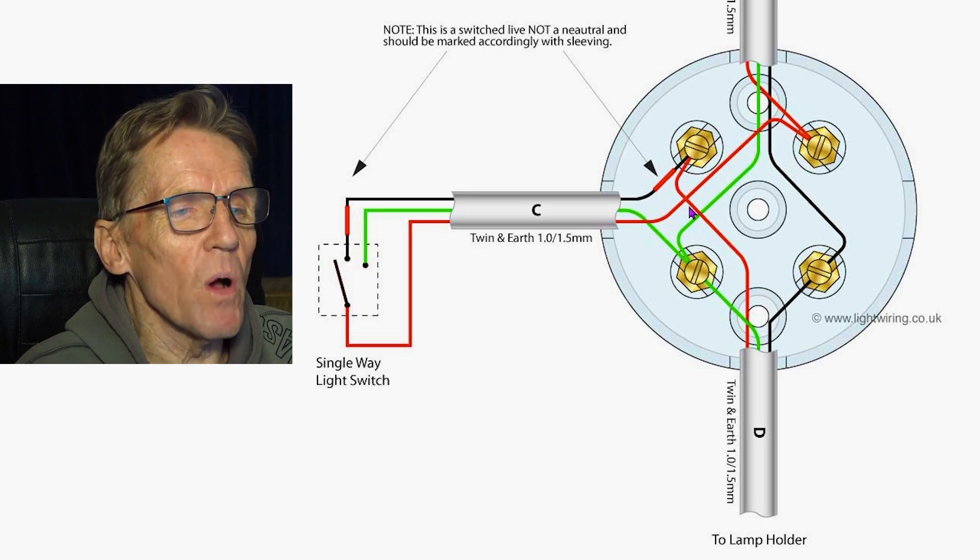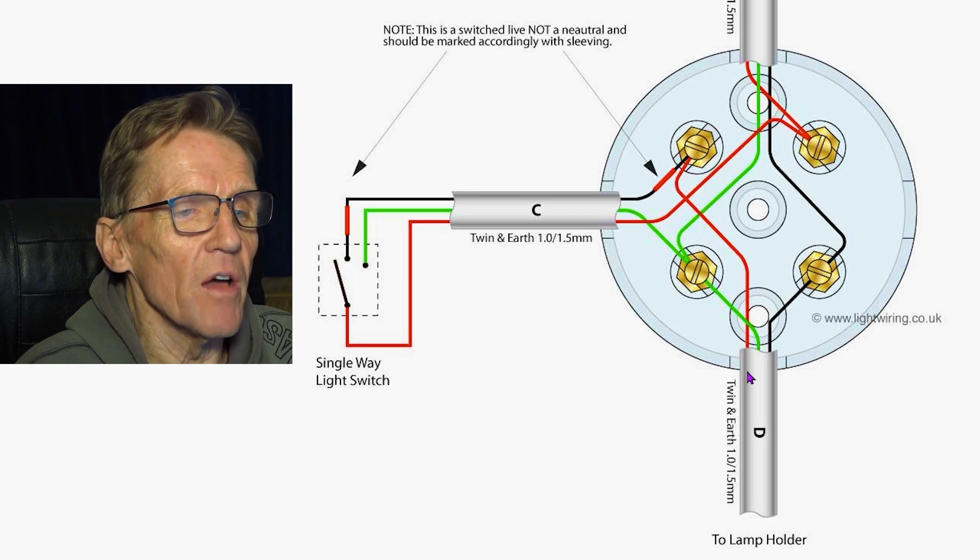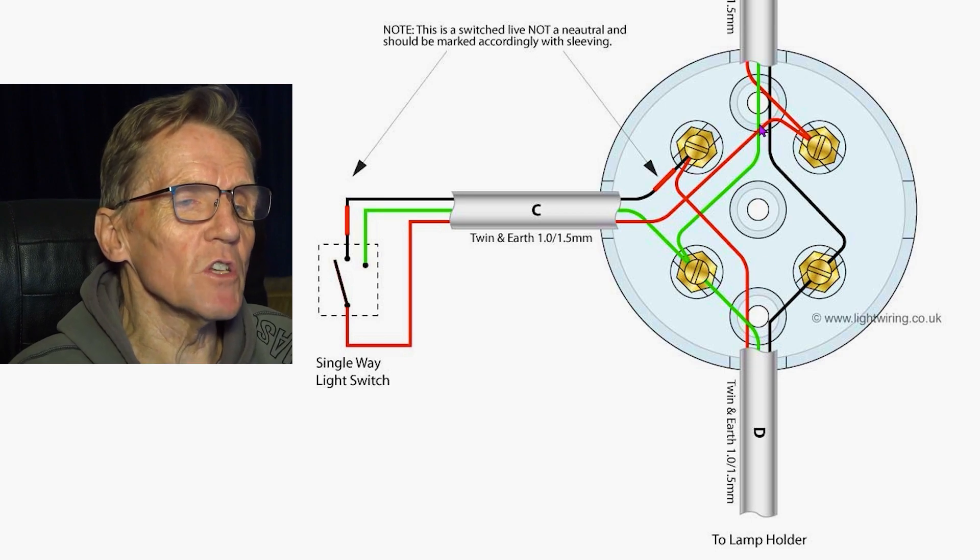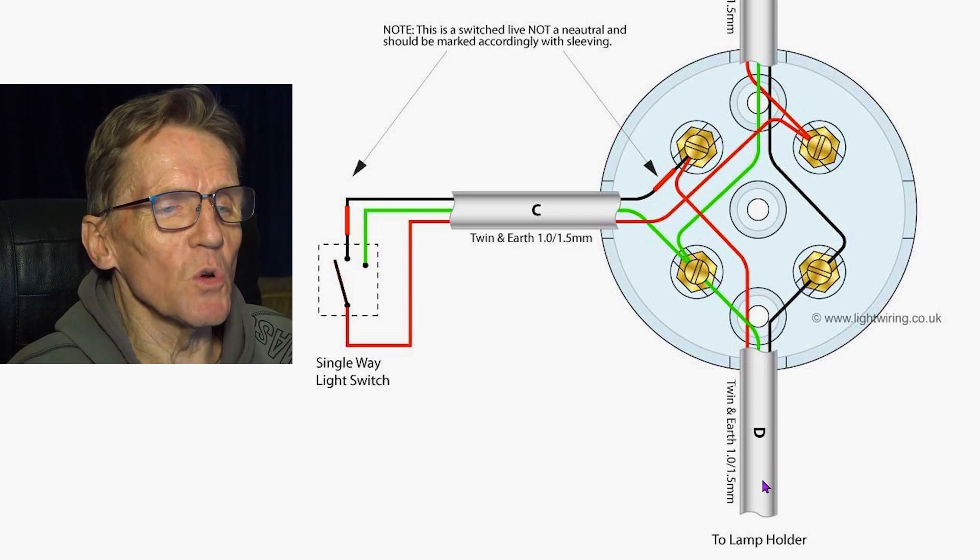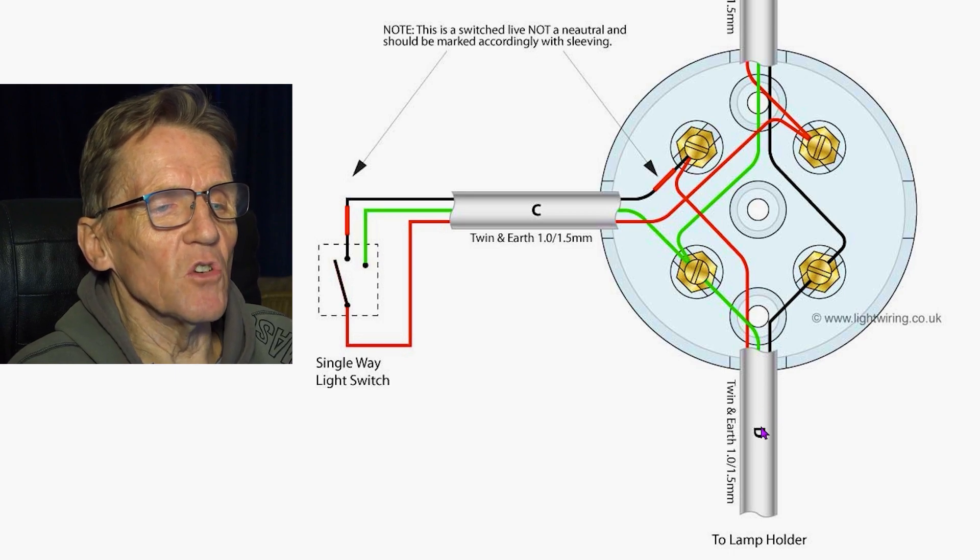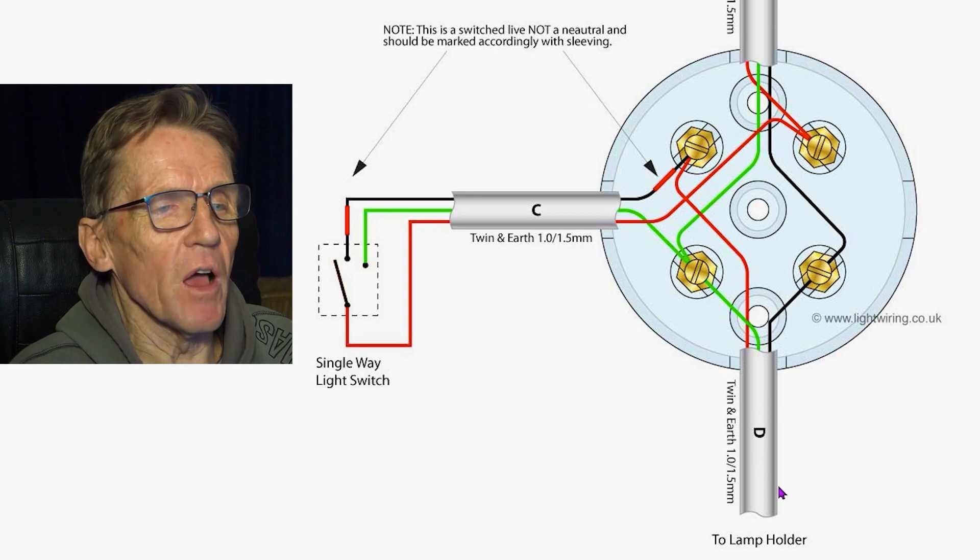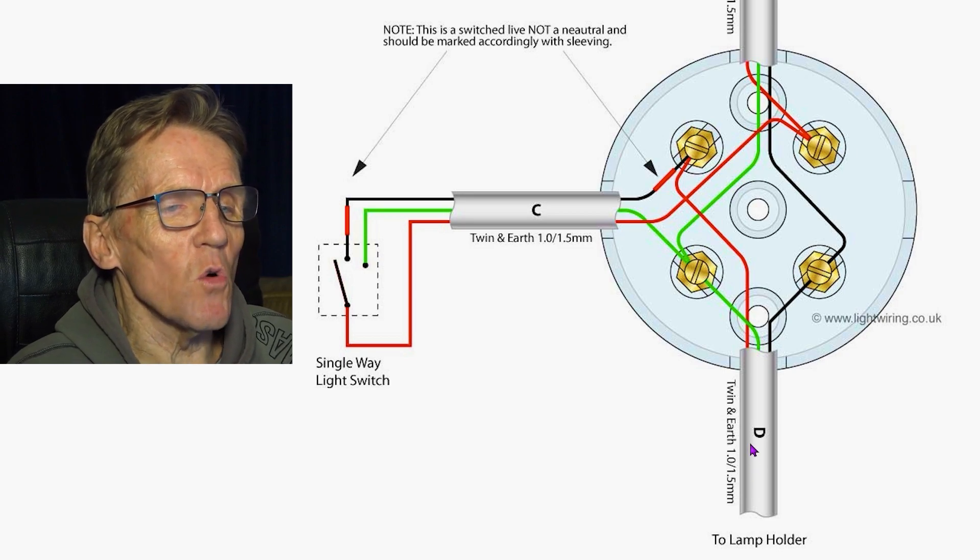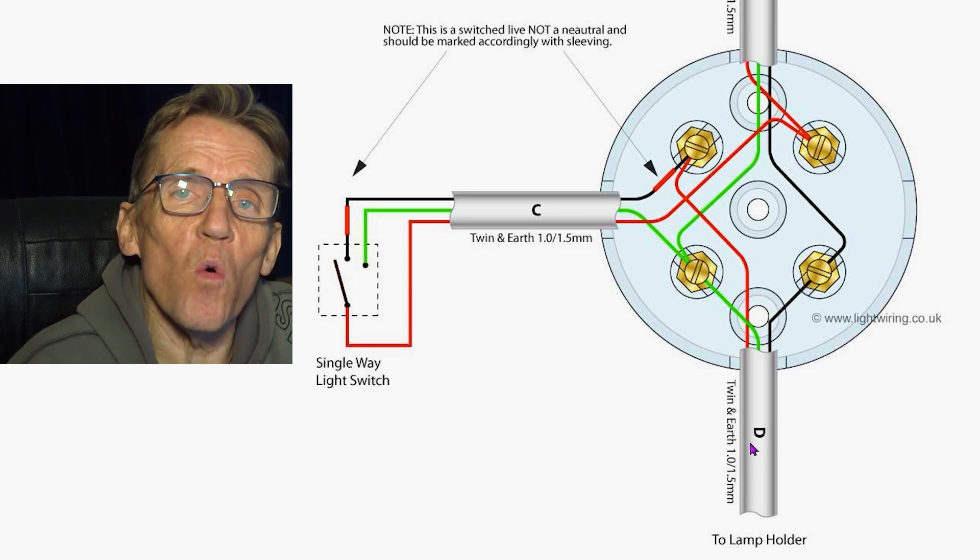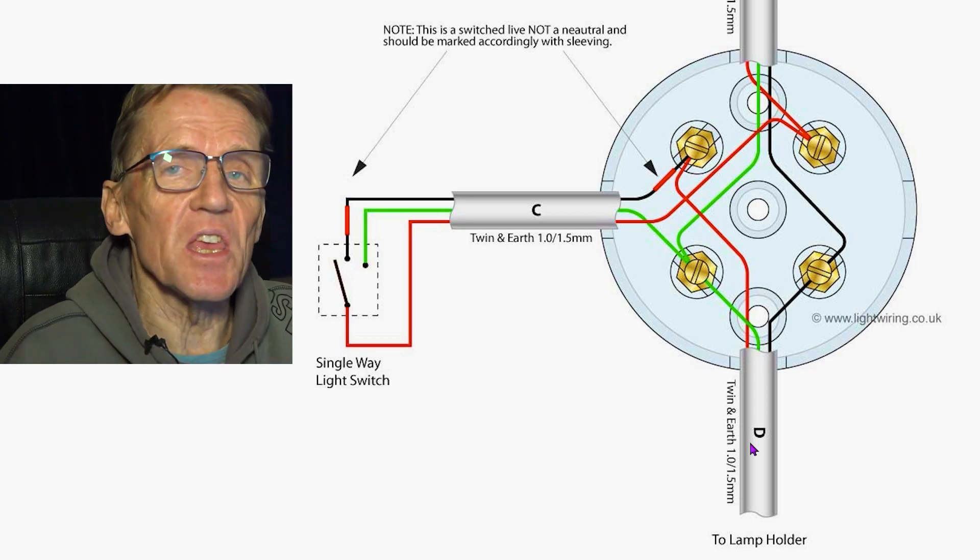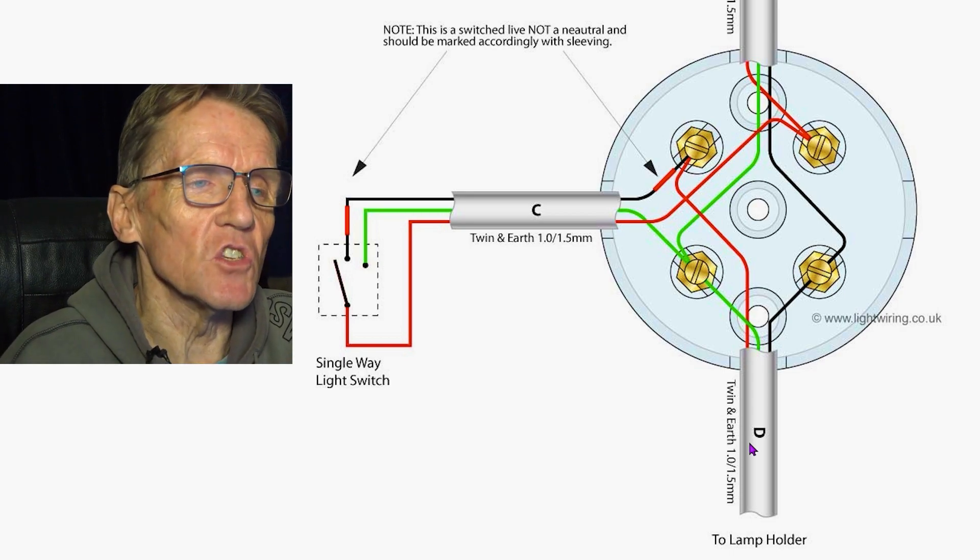And that is the one that is now going down to the live. Now the reason we do this, the reason we have this system like this rather than putting a switch on the actual—you could just put a switch straight on there if you like—but the reason we don't do that is because we like to rationalize all the connections and make sure that all the connections are actually in accessible places.